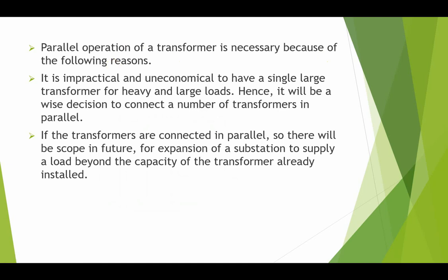It is uneconomical to have a single transformer for heavy and large loads, so it is wise to connect a number of transformers in parallel. If a single large transformer develops a fault, we have to disconnect all supply; but with multiple transformers in parallel, we can shift the load to the other transformers in the system. Also, if transformers are connected in parallel, there is scope for future expansion of the substation to supply loads beyond the capacity of the transformers already installed.